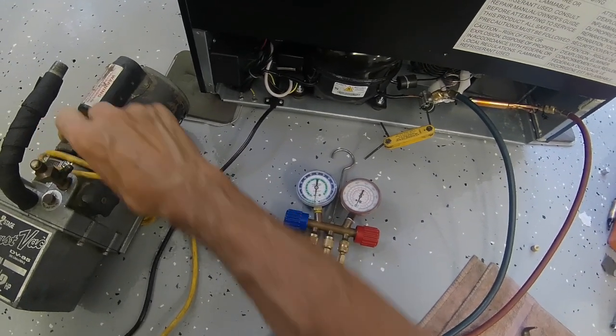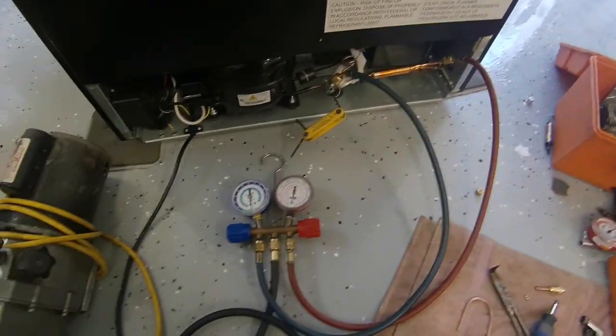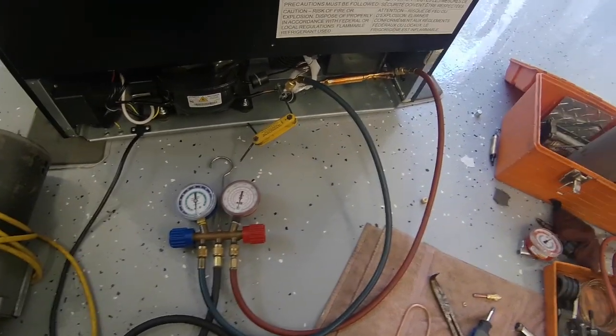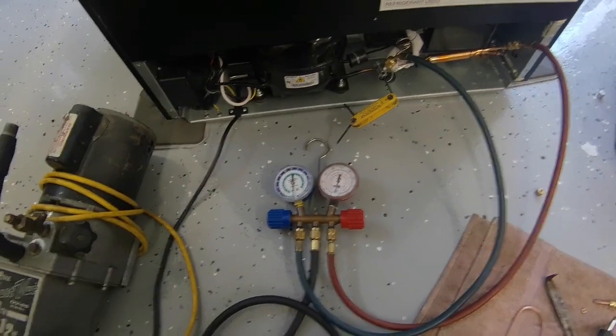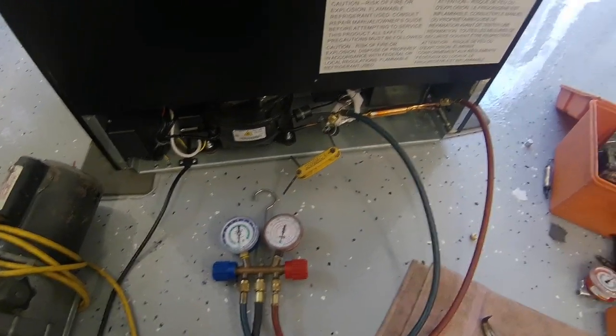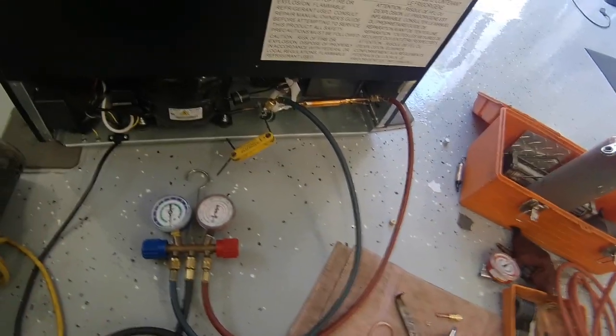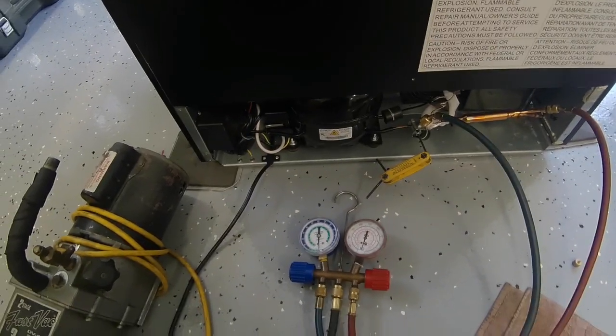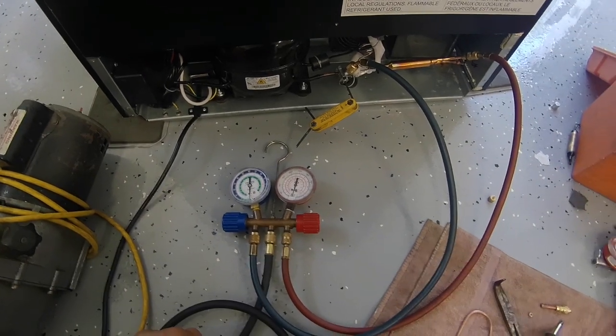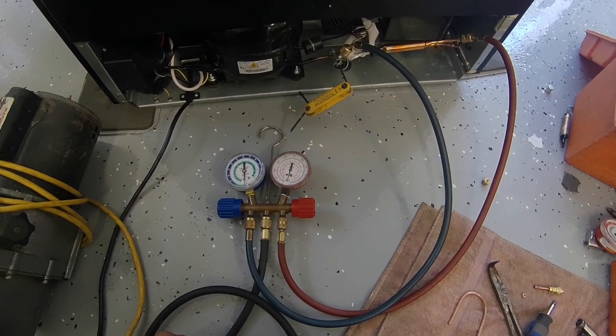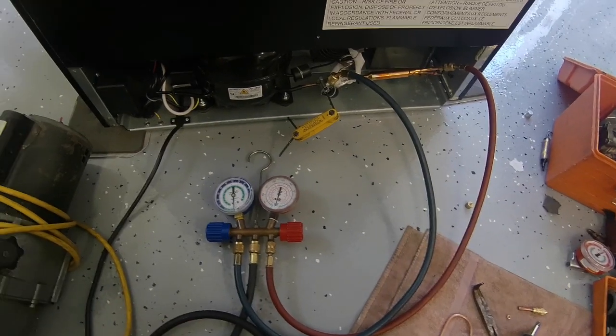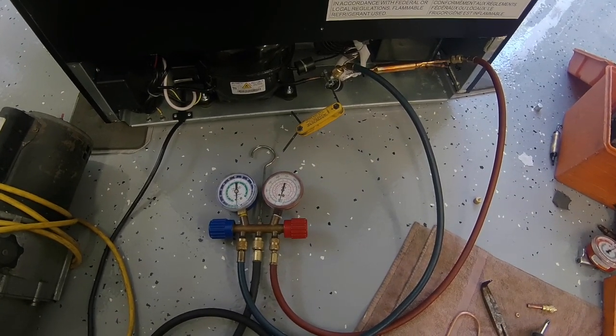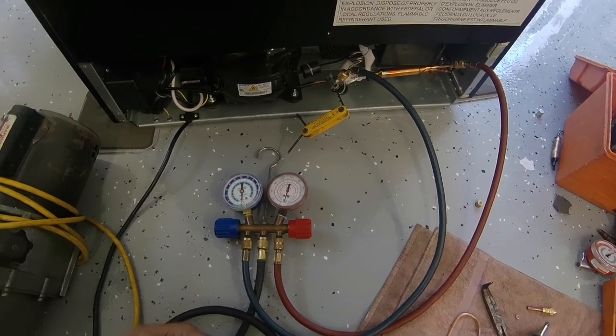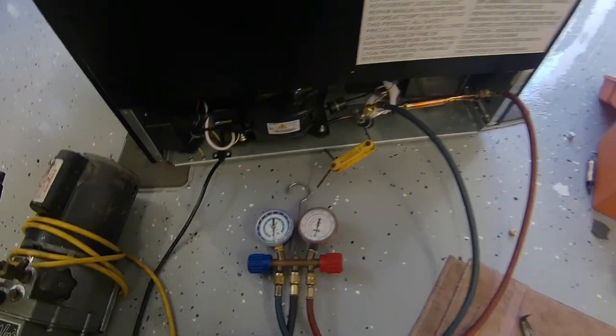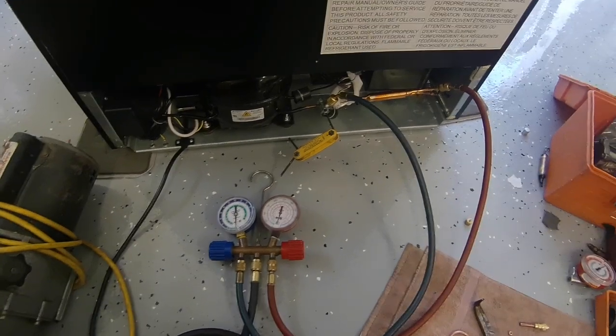Now we know the system's empty. My next thing is I'm just going to weigh 1.96 ounces of gas in there and give it a shot. If that doesn't work, I don't know what I'm going to do. I still hear the gurgling noise inside, even though we got some more refrigerant out, so I'm thinking maybe it's oil, or there could have been moisture in the system if it had a leak. I'm not sure, but we'll charge it up and see where we get.